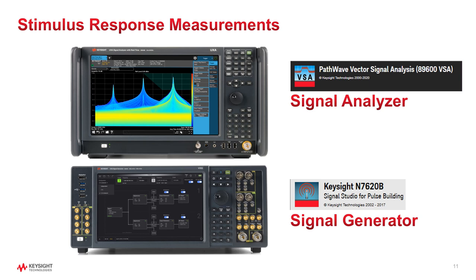For the purposes of evaluating your transmitter, you're going to need a high-performance spectrum analyzer. For the purposes of evaluating your receiver, you'll need a high-performance signal generator. Having them both together is a great way to test out your pulse signal creation and measurement algorithms. For example, you can set up a fairly realistic antenna scan pattern and then verify that by putting the spectrum analyzer in zero span. The setup also enables you to study the effects of a single component like an amplifier — sometimes the amplifier can get hot and have residual memory effects due to temperature that lead to distance estimation uncertainties. Why not send the exact same signal you plan to use on your amplifier rather than some CW representation at a similar frequency? That would be much more realistic.